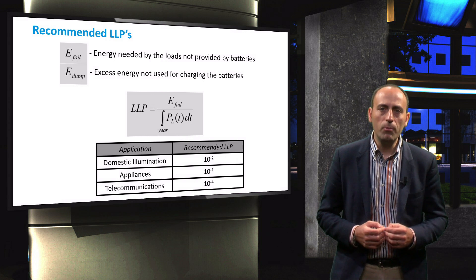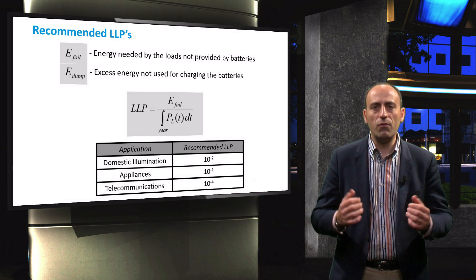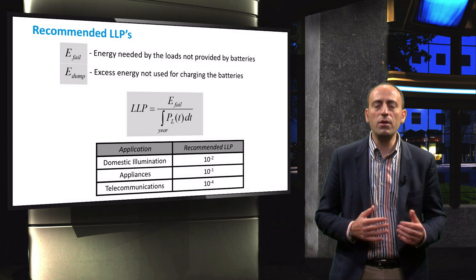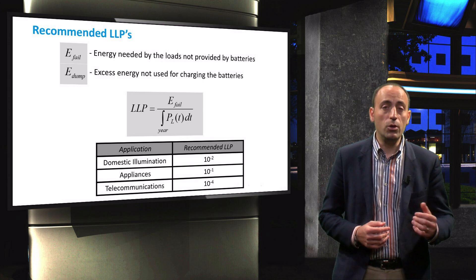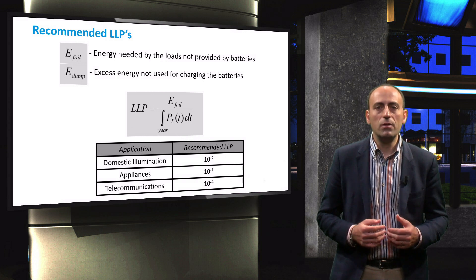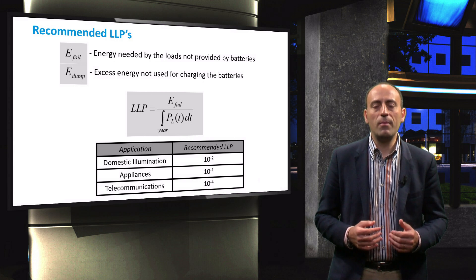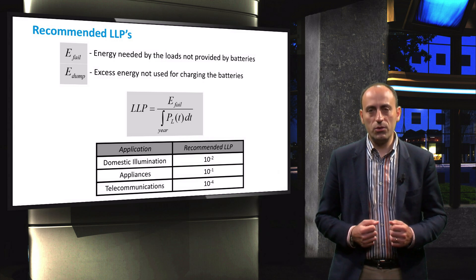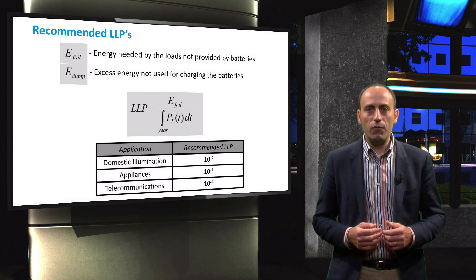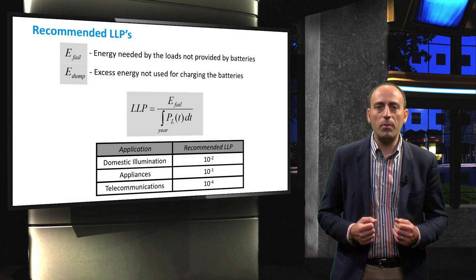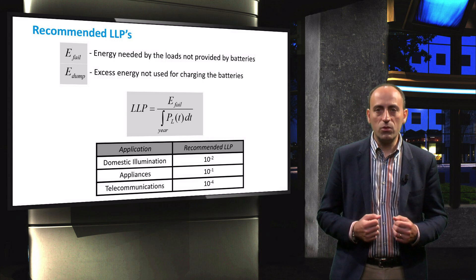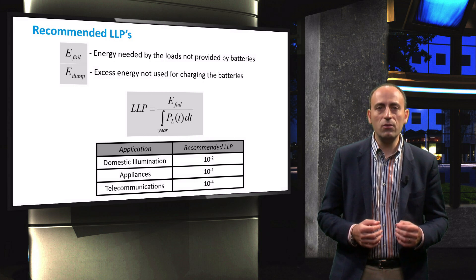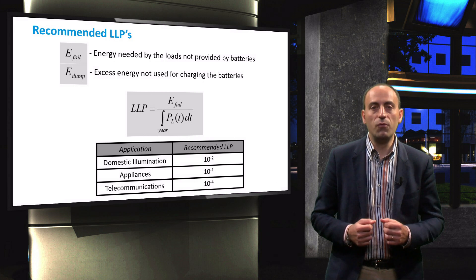This table provides typical values of recommended LLPs for different applications. For illumination, the typical recommended LLP is 10 to the power of minus 2. For appliances, it is 10 to the power of minus 1, and for telecommunication, it is 10 to the power of minus 4.